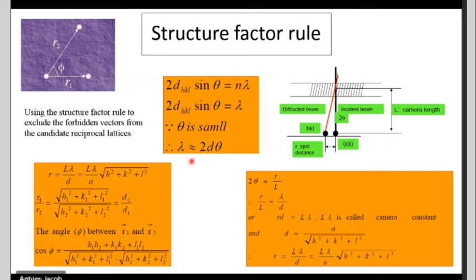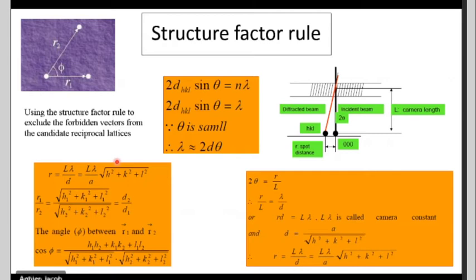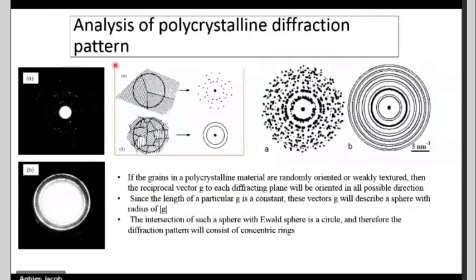In a typical diffraction spot, you get the (000) direct beam, and after diffraction you get spots corresponding to hkl planes. The camera length L is the distance between the specimen and the viewing screen. In TEM instruments, the camera length is pre-calibrated and given in reciprocal units — the ring radius is inversely proportional to the d-spacing. In the image you get a scale bar in reciprocal space units.